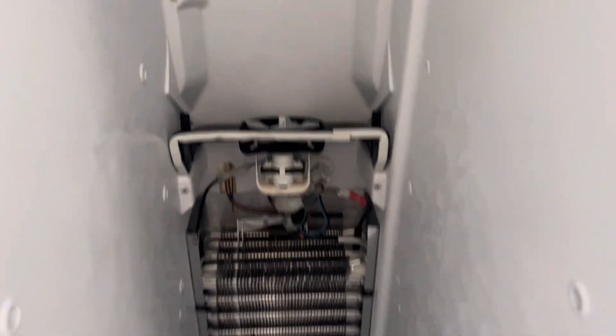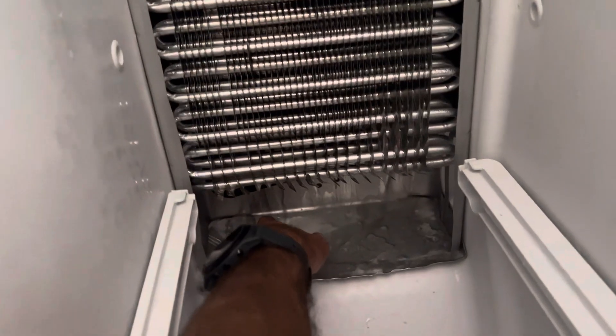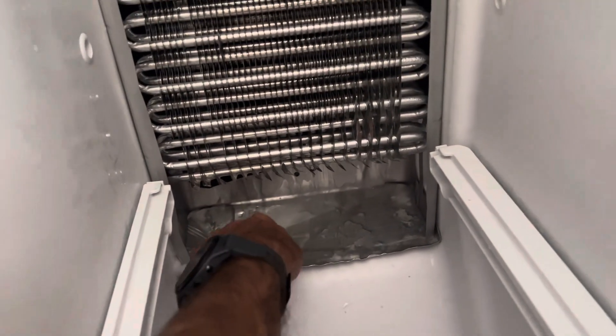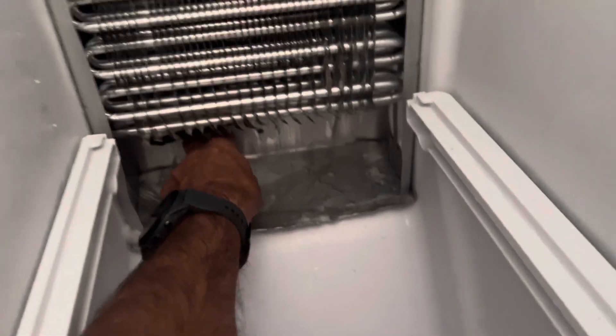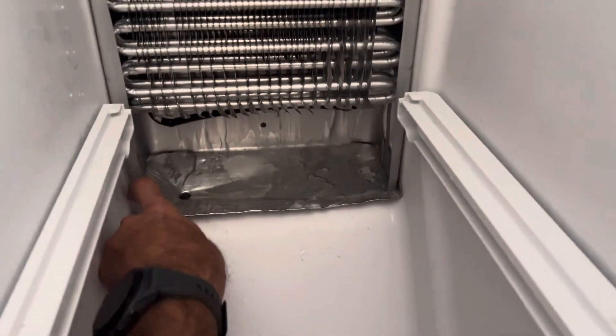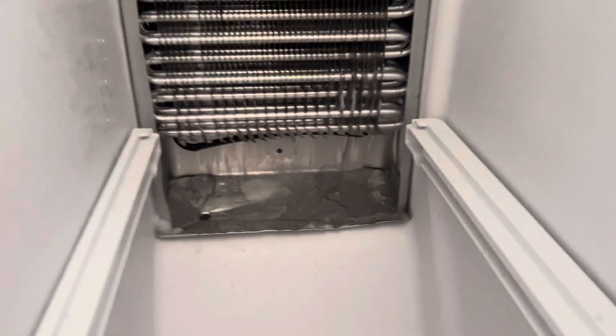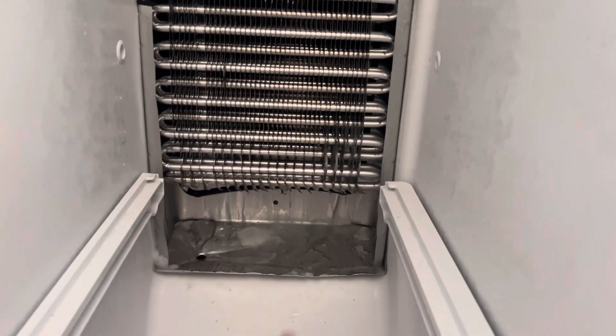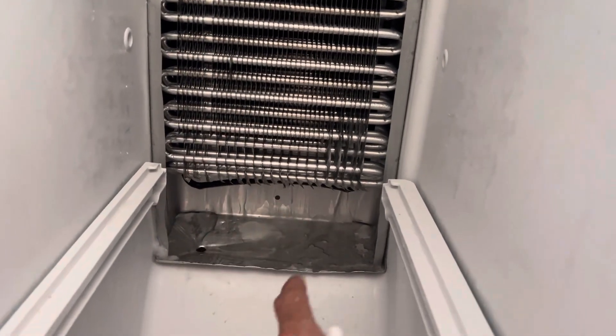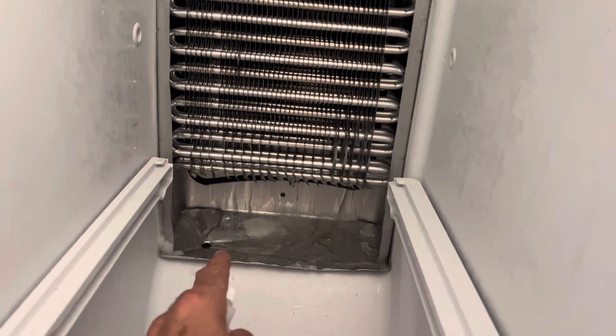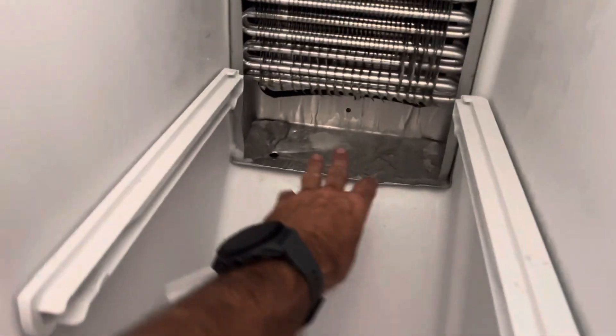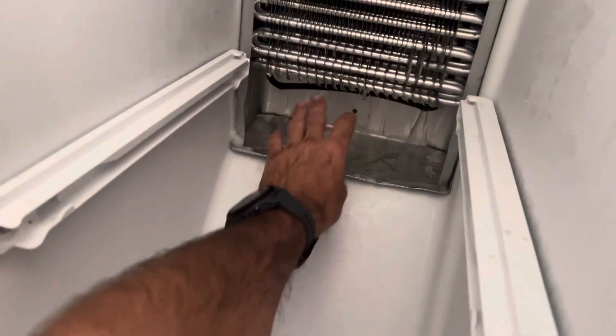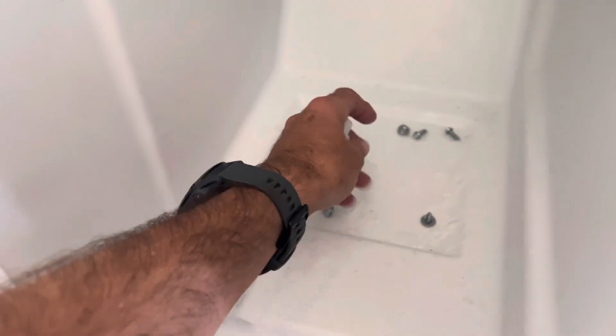Before, I was just taking it apart, pulling the ice out of the fan so the fan could spin freely. The drain line was plugged up a while back with ice, so I put warm water down there so that the water could drain before it freezes.